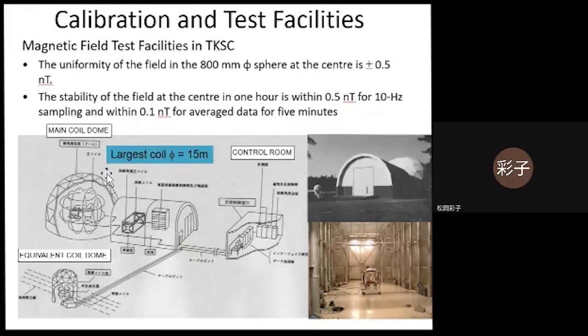Because the geomagnetic field varies a little, we need some control of this cancellation magnetic field for stability. The stability of the field at the center of this facility is 0.5 nanotesla, at a frequency of 10 hertz. We make the calibration test inside this test facility.